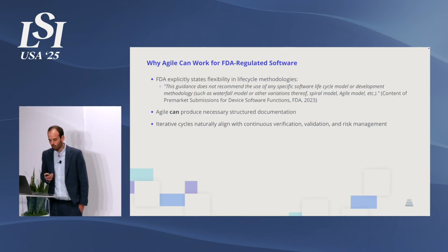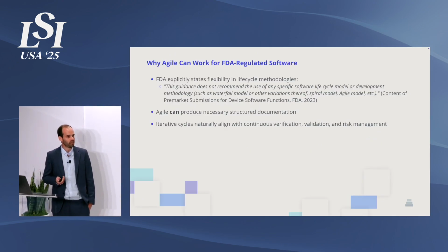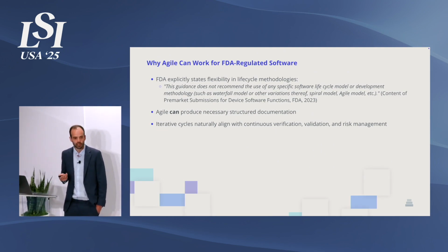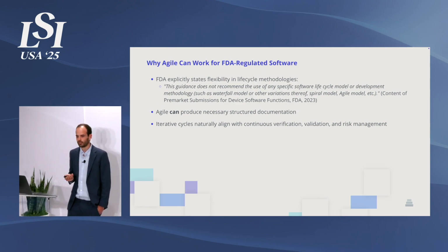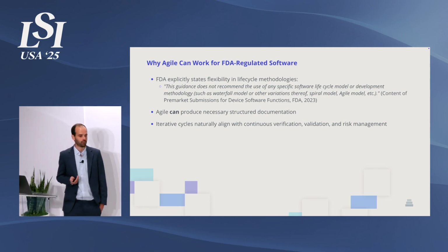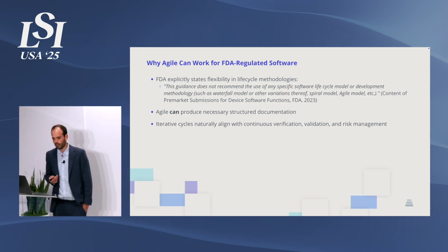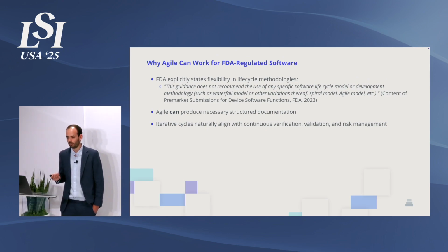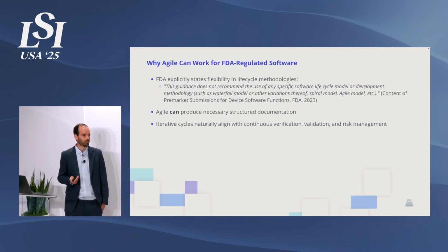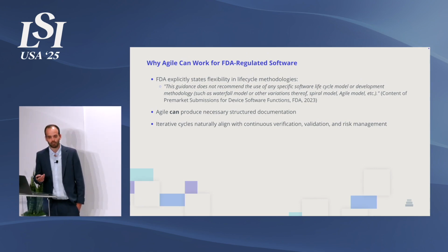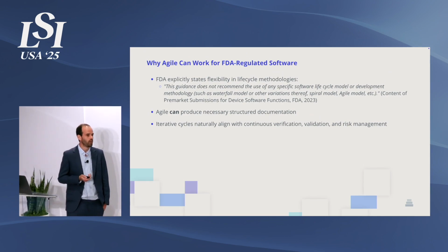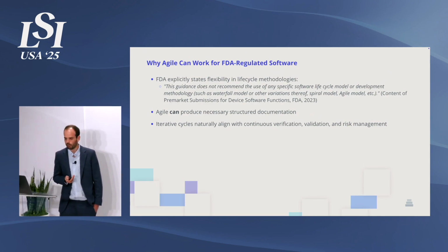One thing we wanted to say is that Agile can be used for FDA-compliant software. There's a myth that it can't be used for FDA-regulated software, and we believe that it can. First of all, the FDA explicitly says it in their Content of Premarket Submissions for Device Software Functions. It says that it even accepts other methodologies like the spiral model, etc. So the FDA explicitly says that, and that's very important.